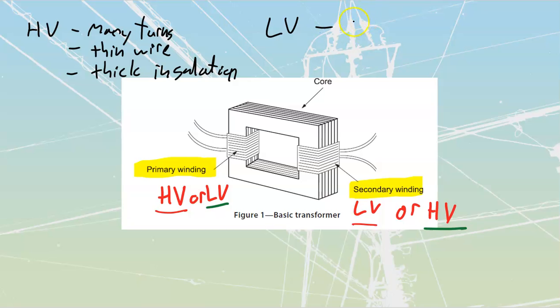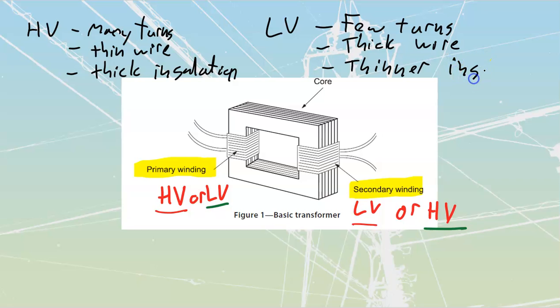A low voltage side is just going to be the opposite. Anytime that we've got the low voltage, we're going to have few turns. Right, ampere turns. We're going to have thick wire because it's going to have a lot of current. So it's going to be thick wire. And we are going to have thinner insulation. It's at a lower value of voltage, therefore it's going to have thinner insulation. Now, in a lot of places, you can't actually tell the insulation on one side from the other because, if it's a 600 volt transformer, everything is usually insulated to 1,000 volts or something like that. But in some of our high voltage ones, we definitely can tell the differences between the high voltage side and the low voltage side from the insulation.